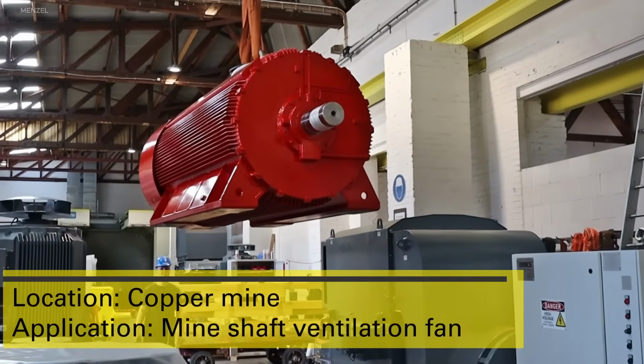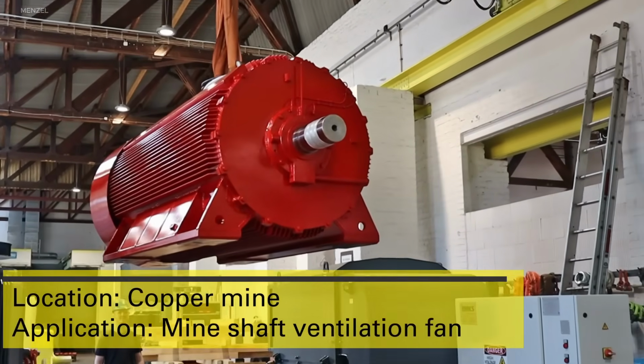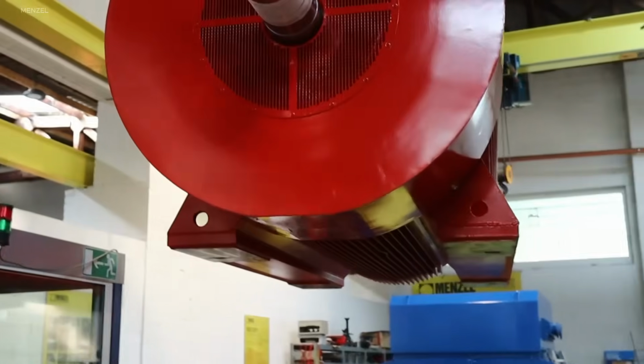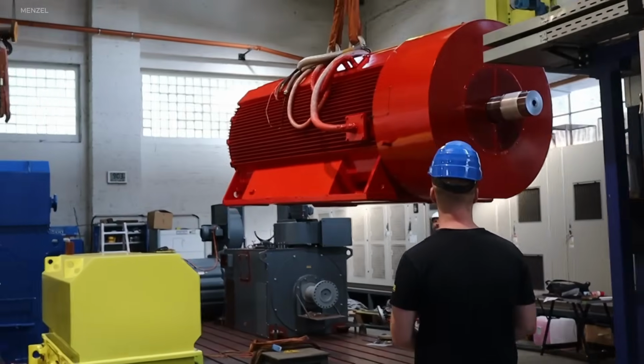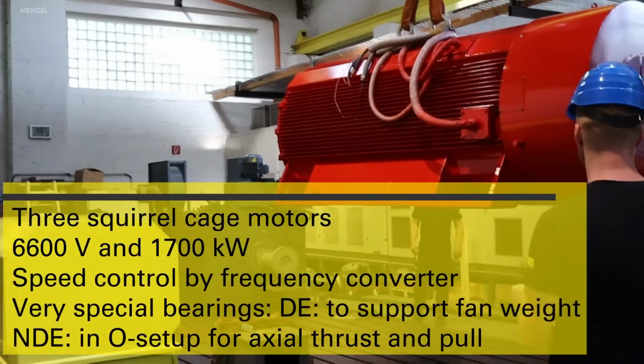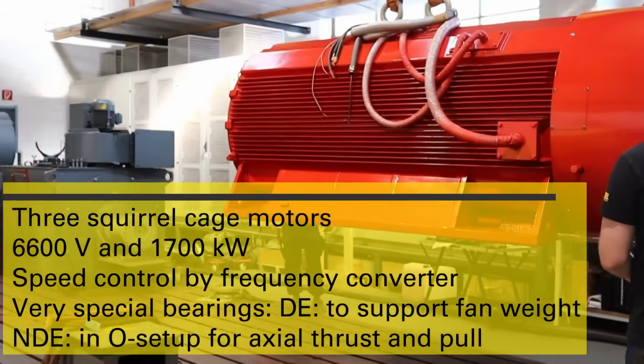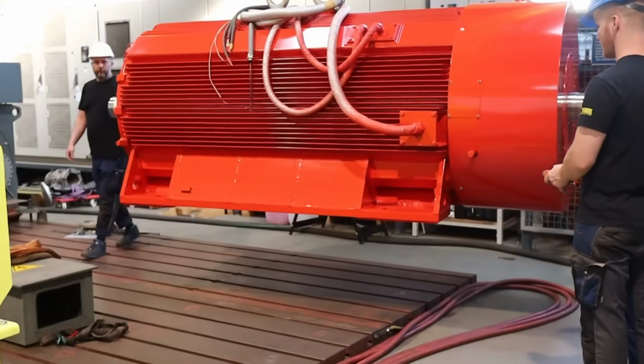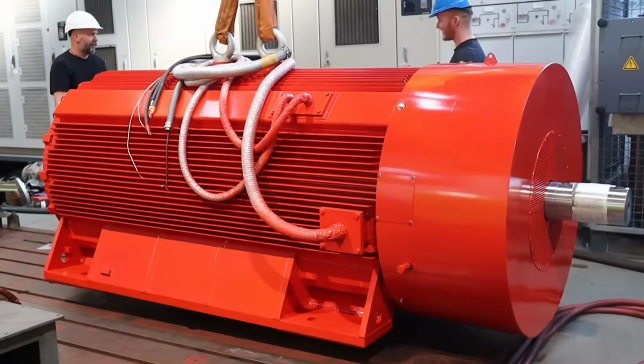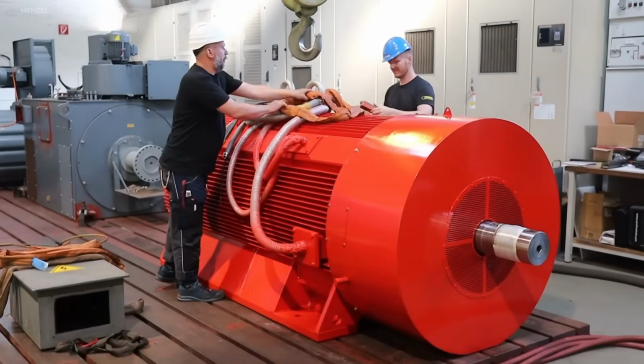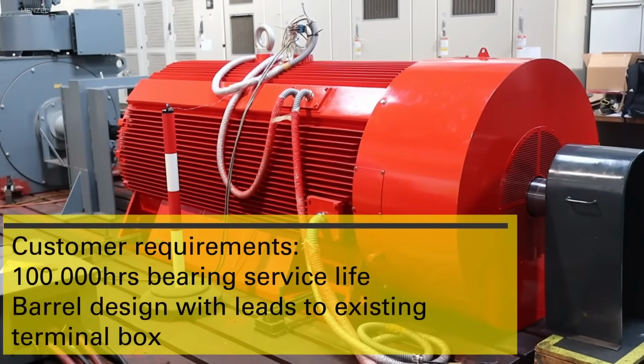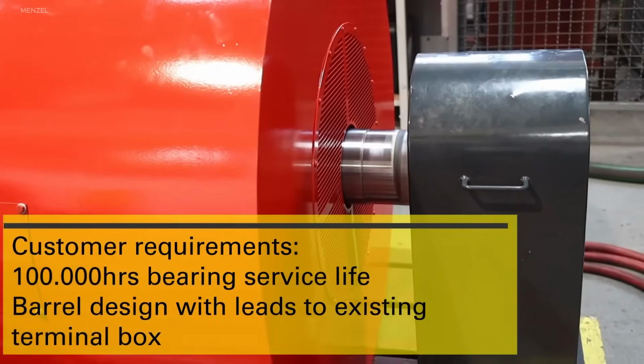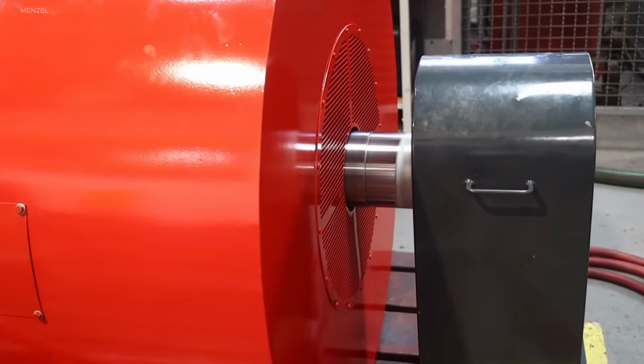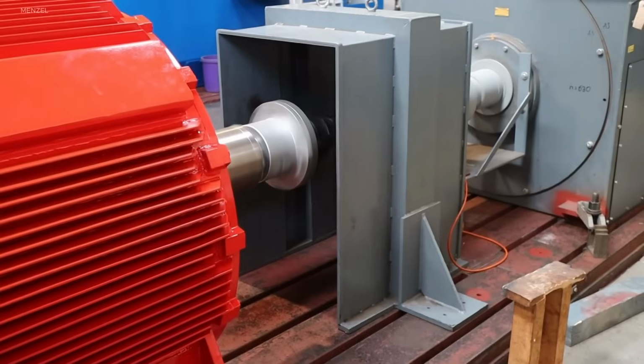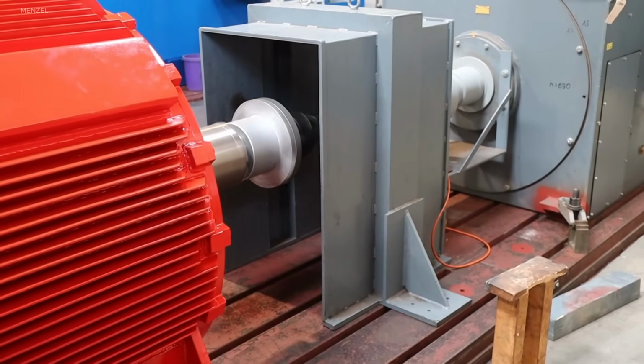Three compact squirrel cage motors, each rated at 1,700 kilowatts and 6,600 volts, drive mineshaft ventilation fans in a copper mine. Using frequency converters, speed is precisely controlled to regulate airflow. The fan wheel is mounted directly onto the motor shaft. The drive end bearing supports the fan's weight, while the non-drive end bearing in O setup handles axial forces. The motors use grease-lubricated roller bearings designed for 100,000 hours of operation.